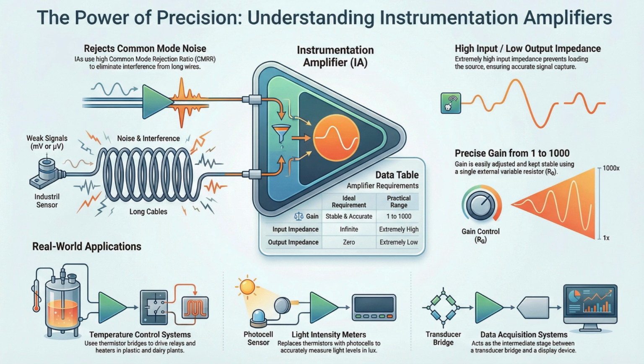That is common mode. Now imagine your scenario. You've built a system with perfect input impedance. You haven't loaded the bridge, but you have poor CMRR. The signal was clean leaving the sensor, but by the time it travels 50 feet to the control panel, it is riding on top of a 5-volt spike from the pump turning on. If the IA can't subtract that spike, the temperature reading jumps. The control system thinks the milk is boiling and shuts down the pasteurizer. Or worse, it thinks the plastic is too cold and turns on the heater, burning the entire batch. In that moment, the high impedance didn't save the batch. The subtraction saved the batch.